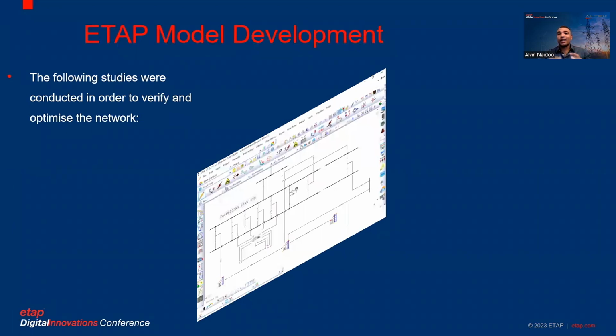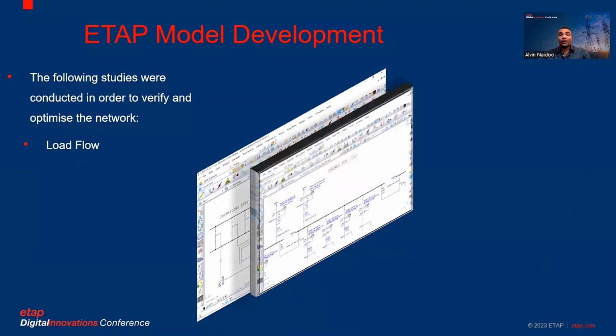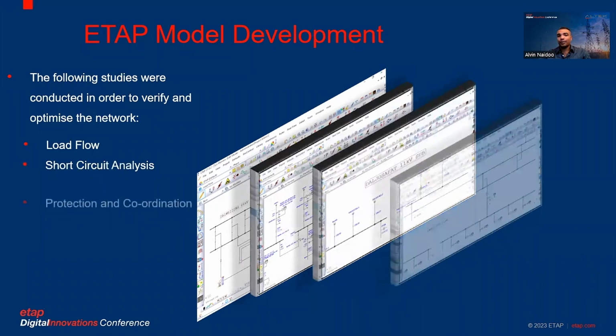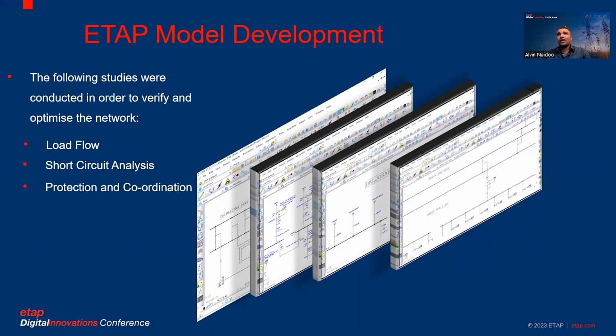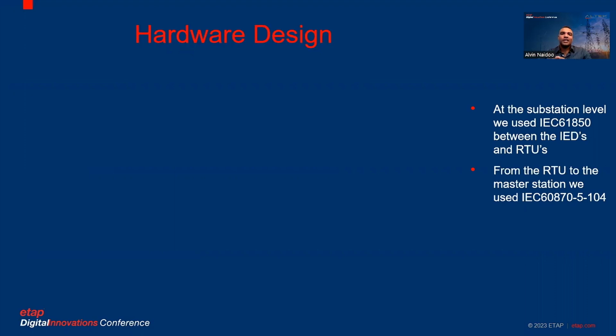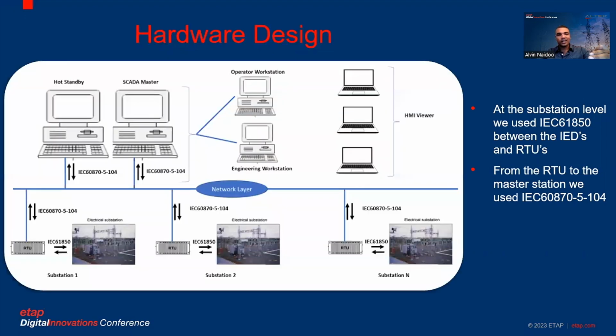So once we had our models developed and accurate information was inputted into the system, we decided let's optimize the network and verify it. So we conducted a load flow analysis, a short circuit study, and a protection and coordination study just to verify the philosophy that was available, which led us now to move on to the hardware design. So at the hardware design, at the substation levels for your newer equipment, we looked at utilizing IEC 61850 between IEDs and RTUs. From the RTU, we looked at utilizing IEC 60870-5-104 to the master station, which led us to an architecture like this.